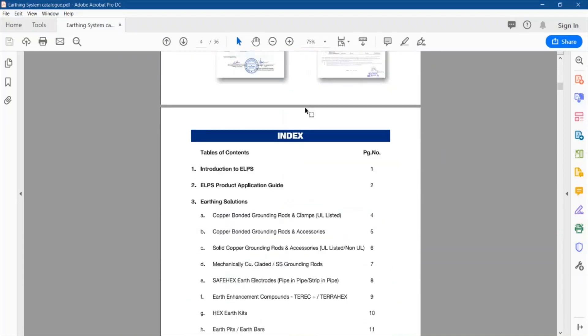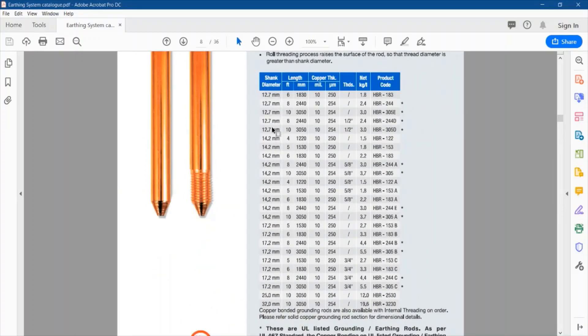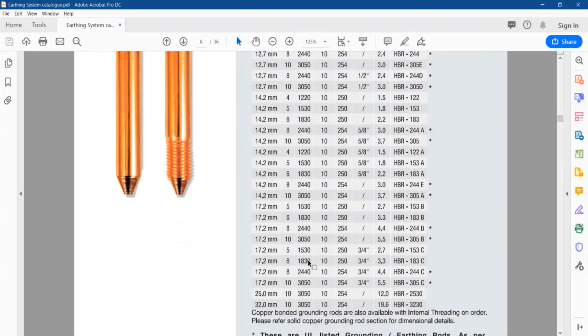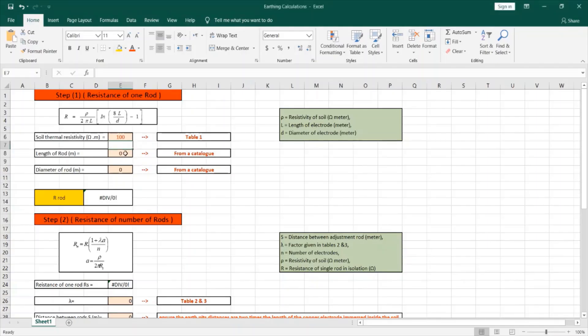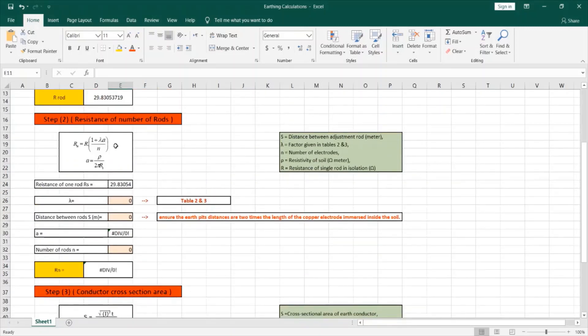From the catalog we can choose among different lengths and diameters of electrodes. I will go for the highest length available, which is 3 meters, with a diameter of 32 millimeters. Going back to the Excel sheet, I'll enter a length of 3 meters and a diameter of 0.032 meters — remember to convert millimeters to meters. As you can see, we got a resistance value for each rod of 29.8 ohms.